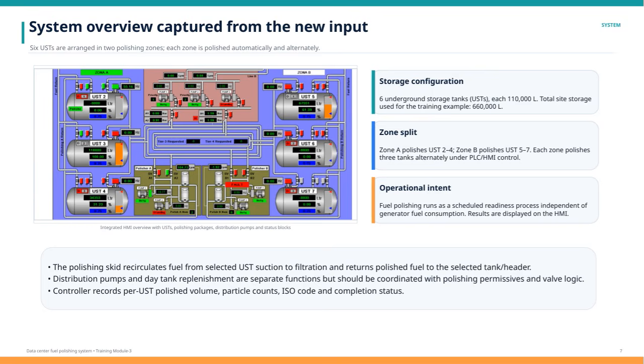It's important to note that distribution pumps and day tank replenishment functions are separate, but they must be coordinated carefully with the polishing permissives and valve logic to ensure smooth operation. Finally, the controller records detailed data for each tank, including polished fuel volumes, particle counts, ISO cleanliness codes, and completion status, giving a comprehensive overview of the system's performance.